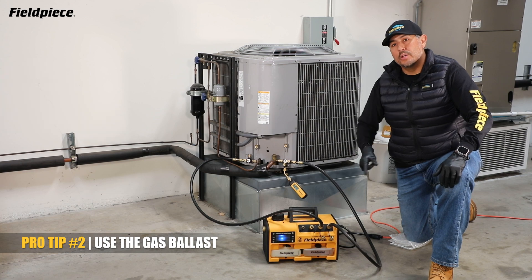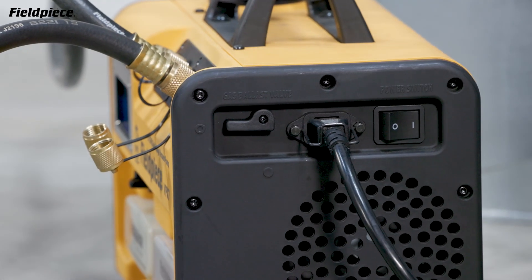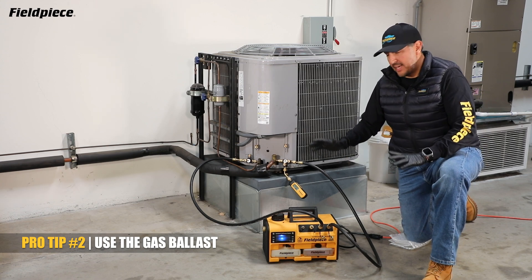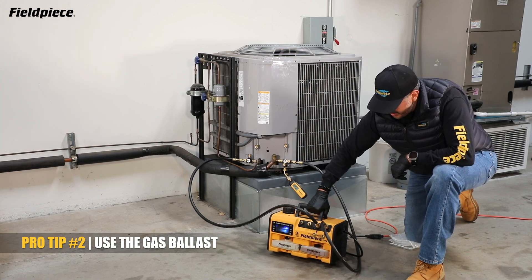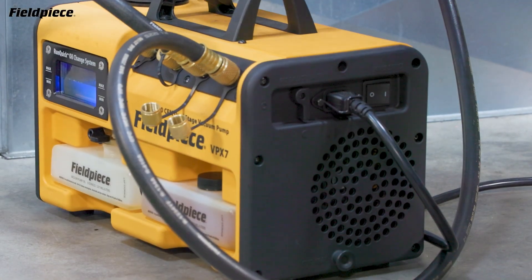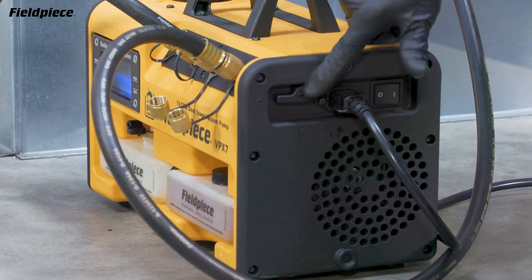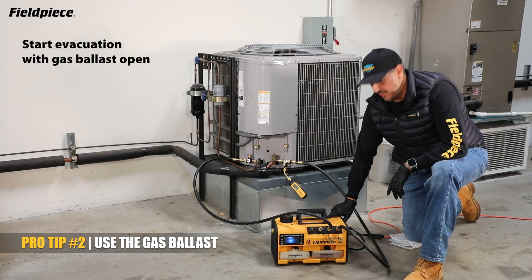Pro tip number two: use the gas ballast to extend the life of your vacuum pump oil. Using the gas ballast properly is pretty simple. Once you're all set up and connected to the system ready to pull a vacuum, you want to open up your gas ballast. On the Fieldpiece pump it's easy — you have a quarter turn knob, turn it up to open up the ballast. With your ballast open, you're ready to start your evacuation.